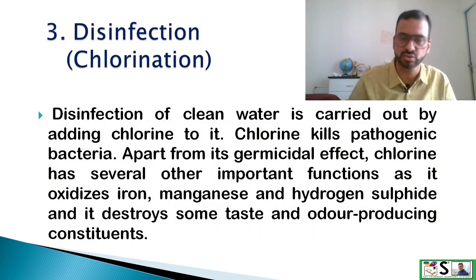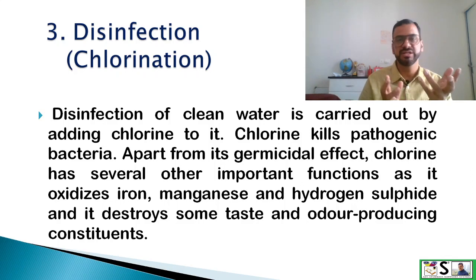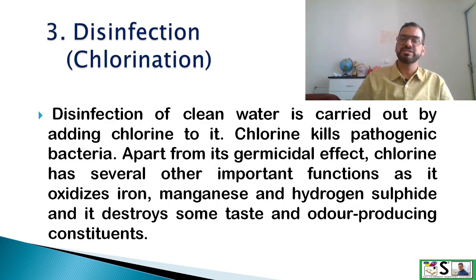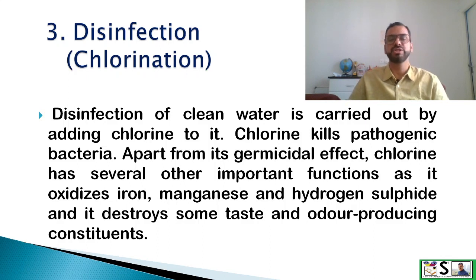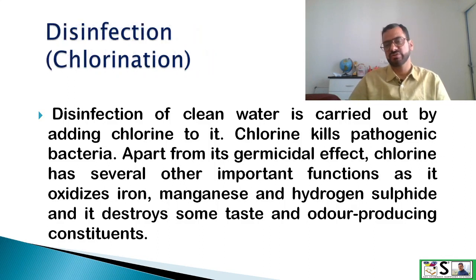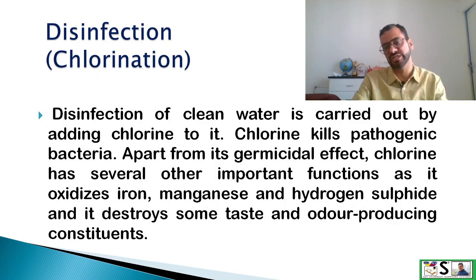The third step after storage and filtration is disinfection. It can take place at two levels: pre-filtration chlorination (pre-chlorination) and post-chlorination where facilities are available, or at one stage otherwise. Disinfection is carried out by adding chlorine because chlorine is a bactericide that kills pathogenic bacteria. Chlorine also oxidizes iron, manganese, and hydrogen sulfide, and destroys some taste and odor-producing constituents.